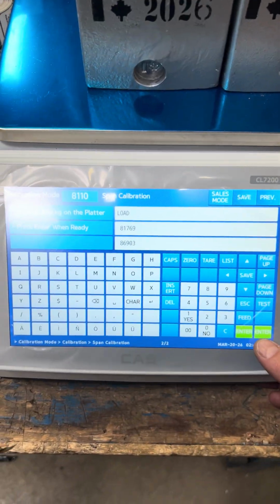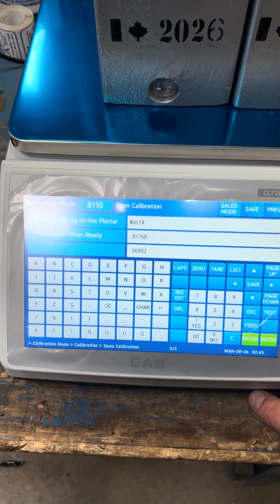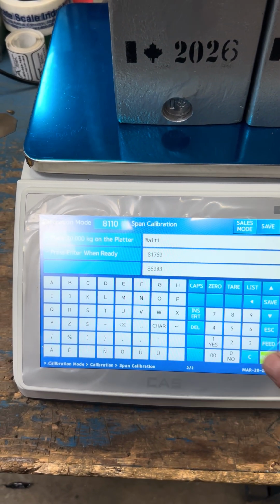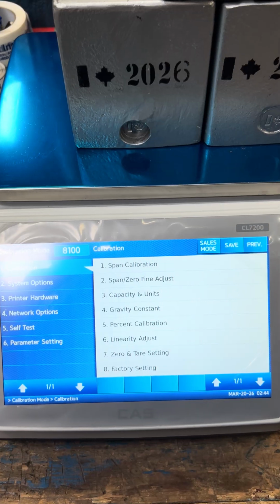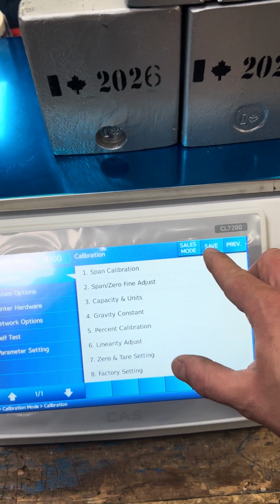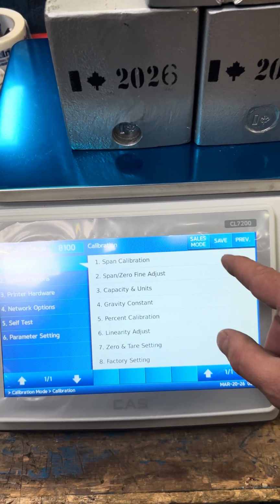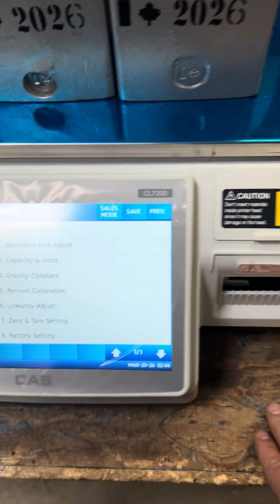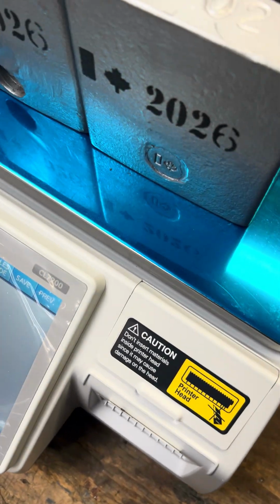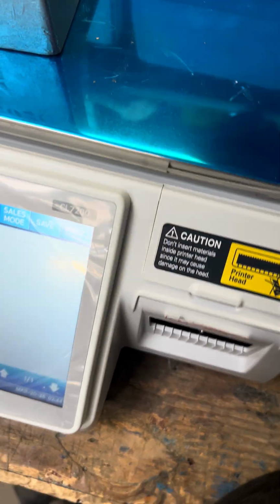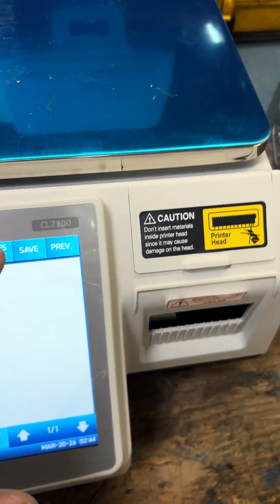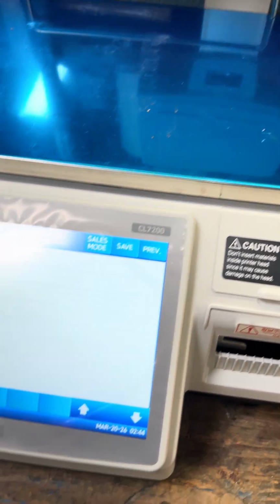Wait a little bit till it's stabilized. Now we press enter button again. It's calibrating and calibration is done. We need to save calibration. And that's all. Now we need to remove the weight and go to the sales mode. It doesn't go, so we need to turn them off.